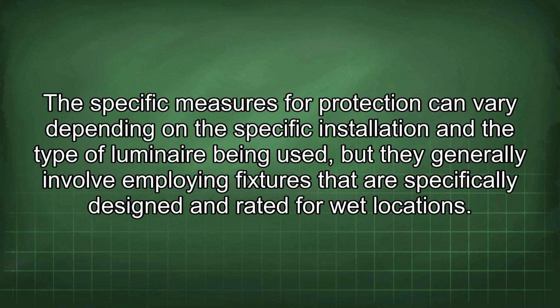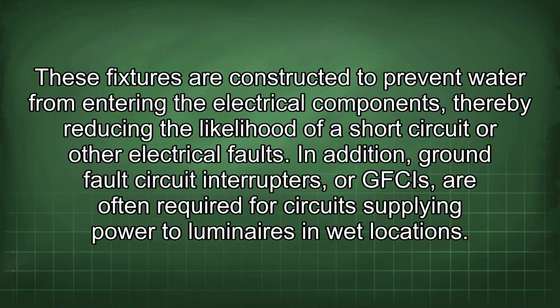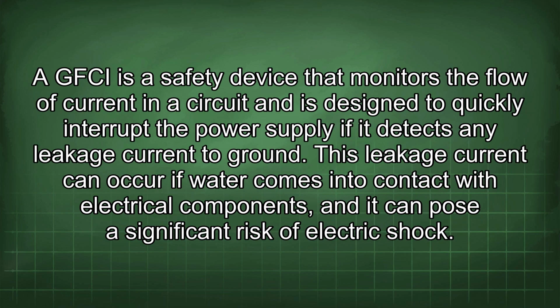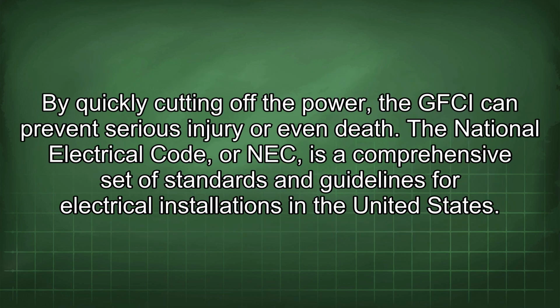The specific measures for protection can vary depending on the specific installation and the type of luminaire being used, but they generally involve employing fixtures that are specifically designed and rated for wet locations. These fixtures are constructed to prevent water from entering the electrical components, thereby reducing the likelihood of a short circuit or other electrical faults. In addition, ground fault circuit interrupters, or GFCIs, are often required for circuits supplying power to luminaires in wet locations. A GFCI is a safety device that monitors the flow of current in a circuit and is designed to quickly interrupt the power supply if it detects any leakage current to ground. This leakage current can occur if water comes into contact with electrical components, and it can pose a significant risk of electric shock. By quickly cutting off the power, the GFCI can prevent serious injury or even death.